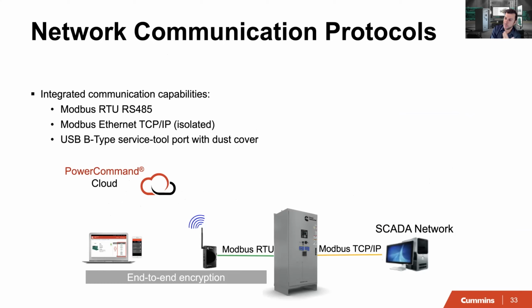Again, the networking is very important. You may want to connect data, pull the data out from the transfer switch and connect that to a SCADA network, but you may also want to connect that into a cloud solution, such as the Cummins cloud solution. So built into the transfer switch control, Modbus communication, whether it's serial over RS-485, and you also have 2 Ethernet ports, which is TCP/IP, and they are Modbus as well. And there's also a service port on the front of the transfer switch, so that a technician can connect and do any settings or modification to the controller, pull data out if they need to.